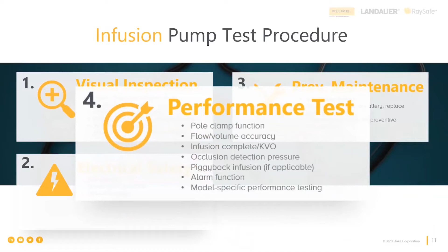With volume flow accuracy, there are several different test instruments or systems that can be used to evaluate the accuracy, flow and volume of infusion pumps. The first one would be the graduated burette, sometimes used with a stopwatch to see the flow rate. The second one would be the beaker and scale system for the volumetric and gravimetric weight, which converts to the volume in the beaker. And the last one would be the electronic burette, the electronic analyzer that already includes the stopwatch function. All of these setups are appropriately accurate to assess the volume and flow accuracy of any infusion device.